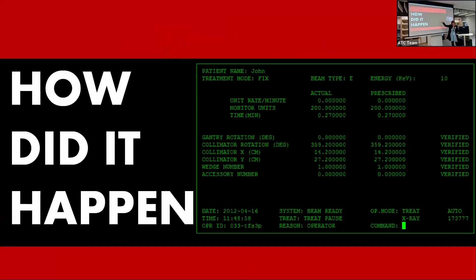Here's an image of what the Therac-25's control terminal would have looked like to the technician. The technician would have selected the mode of operation, selected the amount of radiation that needed to be delivered to the patient, and performed any safety checks that the software gave to them. When they were told it was safe to do so, they would start operation on the patient. Obviously, this is 1983, so the interface was extremely simple and only a limited amount of information could be displayed.